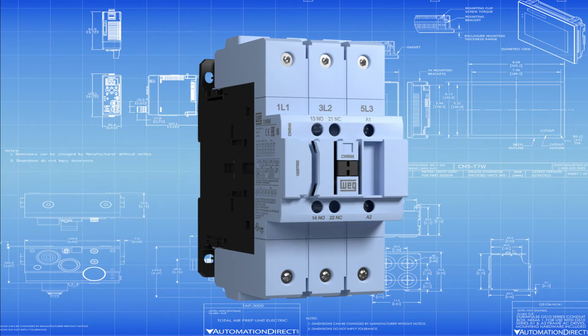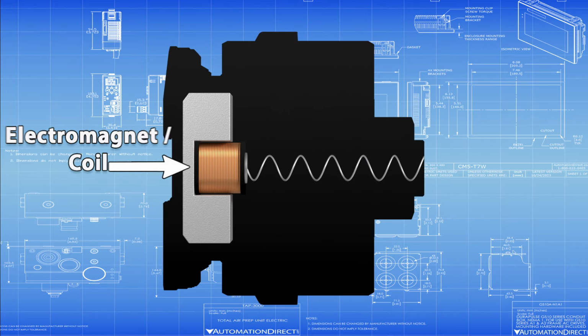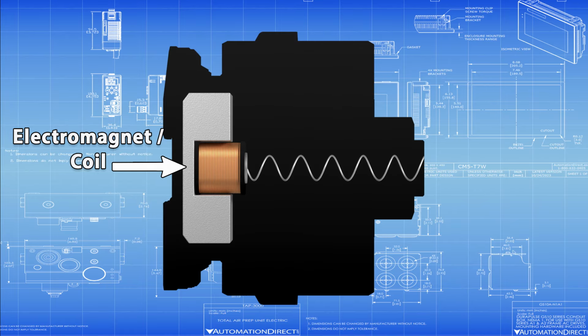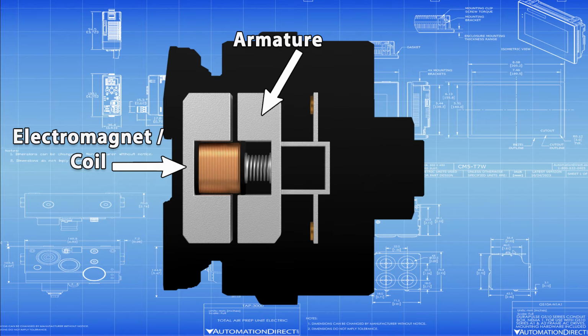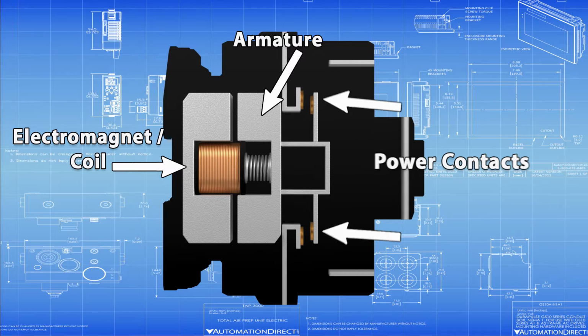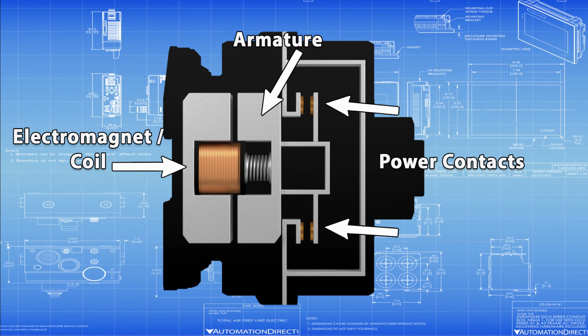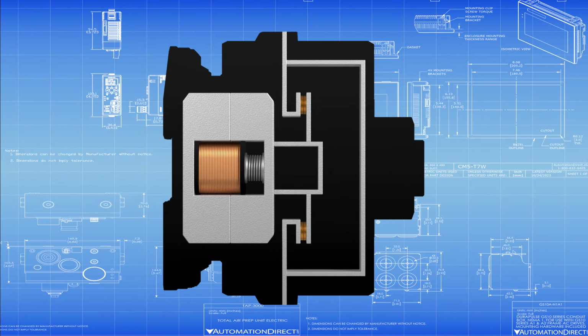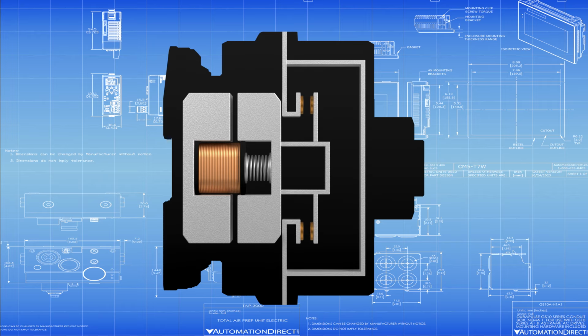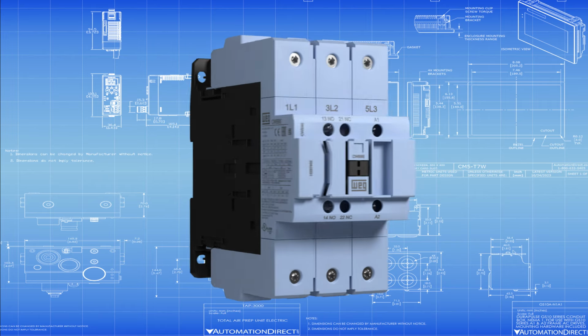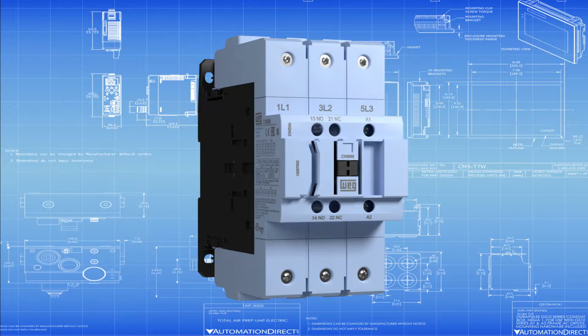safely and reliably. A contactor contains three main components: a coil or electromagnet, which creates a magnetic field when energized, an armature, which is pulled down by the magnetic field, and power contacts, the heavy-duty conductive elements that open or close the load circuit. Applying voltage to the coil pulls the armature down, closing the power contacts and energizing the load. Remove the voltage and a spring forces the contacts open, interrupting the circuit. This design supports high current switching, effective arc management, and long mechanical life.